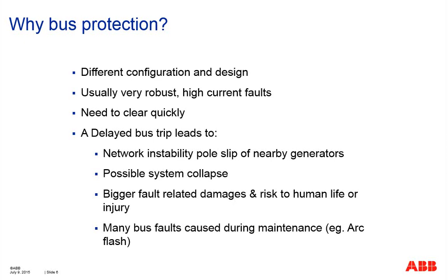Bigger faults are related to damage and risk to human life or injury. That's needless to say. And many busbar faults can be caused during maintenance. When you are doing maintenance work on a metal clad medium voltage switchgear, you accidentally drop a tool or wrench or something. It can cause a damaging arc flash effect. So the busbar protection in that case can save your life.